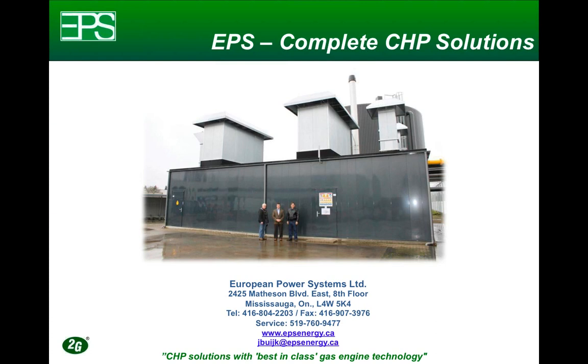Next question: what is the current cost of maintenance for the microturbines? In the past, at about 40,000 hours, you had to replace the turbine core, and we still do. At 40,000 hours is when the turbine core would be replaced, and we offer complete maintenance programs with guaranteed maintenance costs for microturbines at about a penny per kilowatt hour for up to 80,000 hours. It's actually a 9-year contract or 80,000 hours, whichever comes first, at about a cent per kilowatt hour.